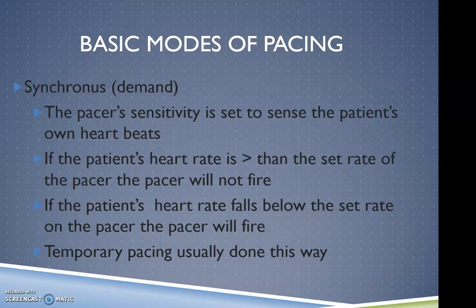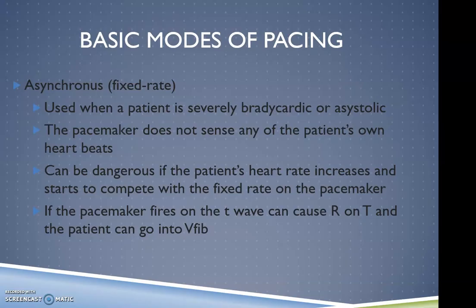Synchronous is demand, meaning it is sensing the patient's own intrinsic activity, and it only fires if it's needed to, aka demand, when it's demanded to. The heart rate falls below a set rate, the pacemaker will kick in and fire. We usually set up our temporary pacemakers this way. Asynchronous is when we're not looking at what the patient's doing, because usually they're not doing much of anything, and we're just going to fire regardless of what they're doing.